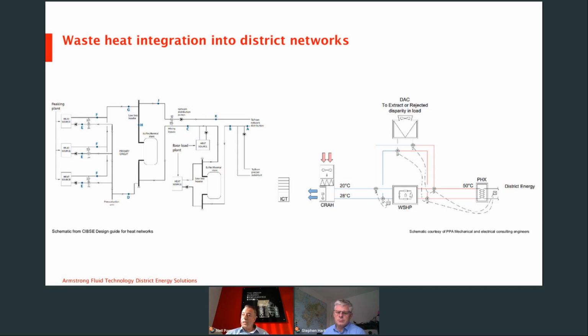On the graphic on the right, we can see a schematic produced by a consultant that we're working with on a waste heat transfer station, taking waste heat from a data center. The cooling return is at 28 degrees C, and this is then utilized by the water source heat pump, raising the output temperature to 50 degrees C for the district network. The dry air cooler is utilized to balance the load differences between the data center output and the district energy demand. While the DAC may at times send some heat to atmosphere, it is important to note that a significant amount of waste heat will be utilized.